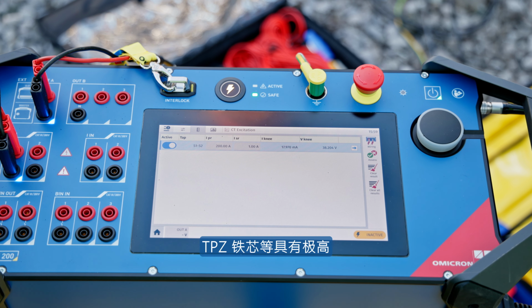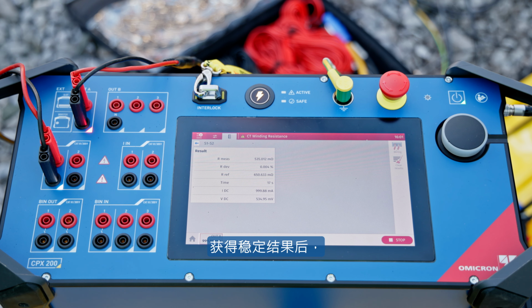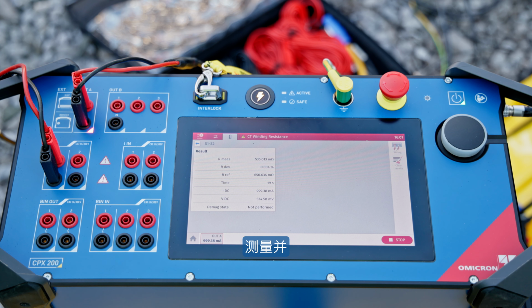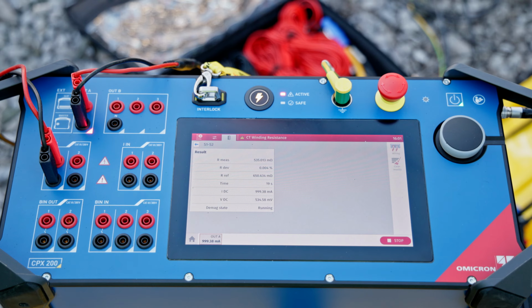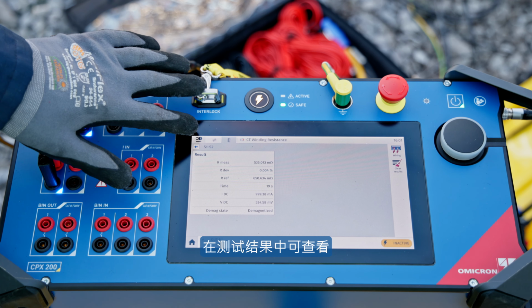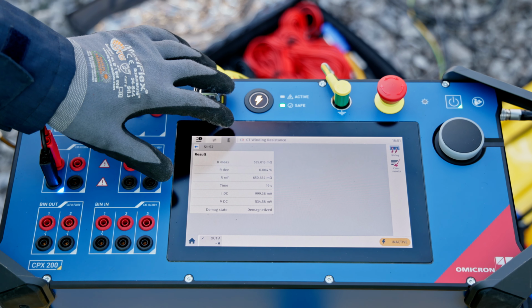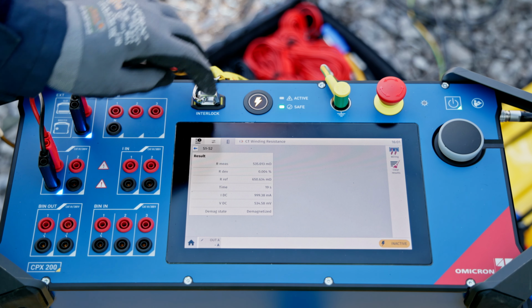The winding resistance test uses output A, which is the most powerful output of the CPX200. It can output pure DC signals without any superimposed hum and lead to very fast saturation with a high compliance voltage. After stable results are obtained, the device automatically stops the measurement and the demagnetization is performed. In the results, you can then see the demagnetization status of the CT. If historical measurement data is available, it can be checked if the obtained results match and even give automatic assessments.